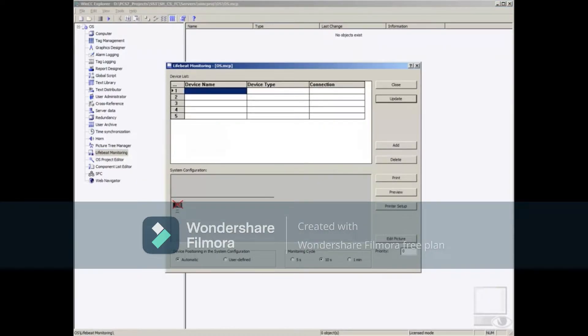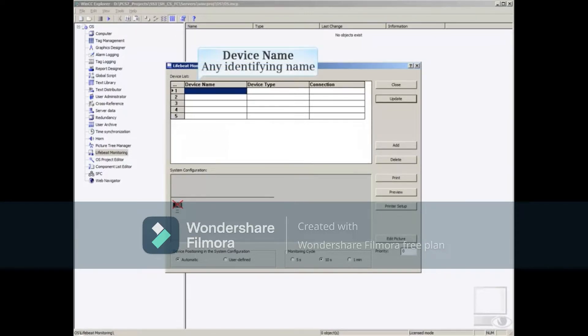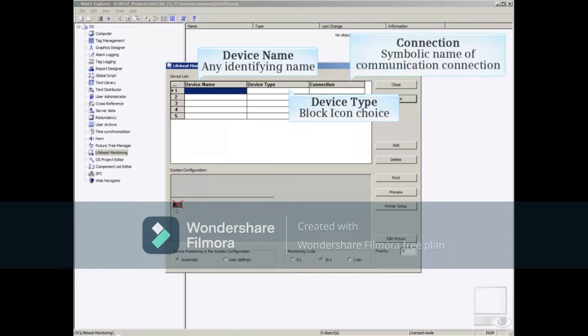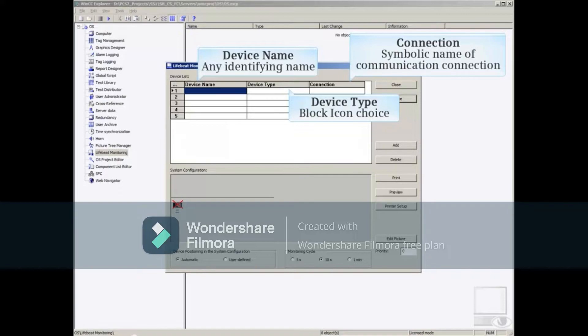At the top of the LifeBeat Monitoring editor, there are three columns. The device name is where you enter a symbolic name of your choosing that the operator will see. The device type allows you to select a block icon that will best represent this device. The connection column is where you select a pre-existing symbolic connection that LifeBeat Monitoring will use to talk to this device.